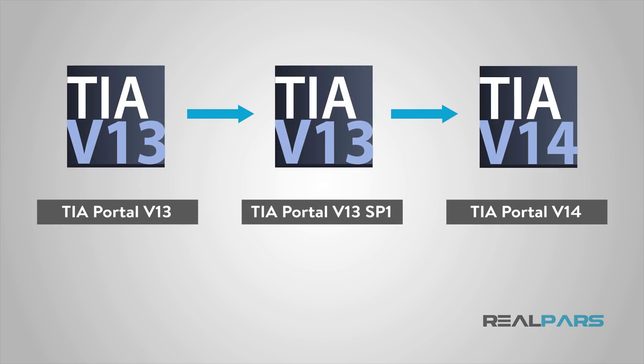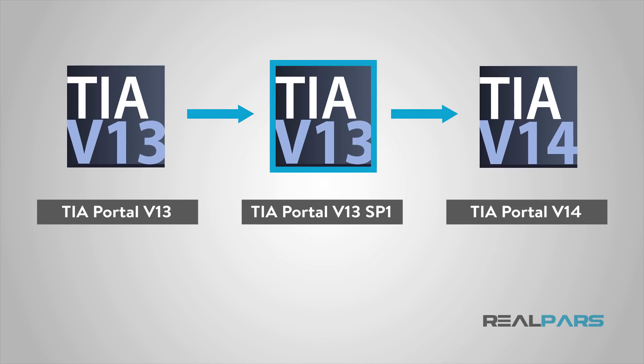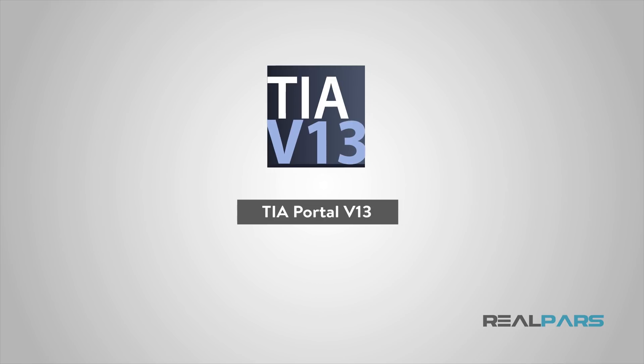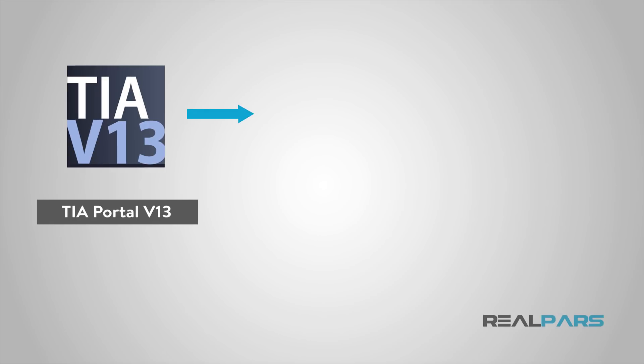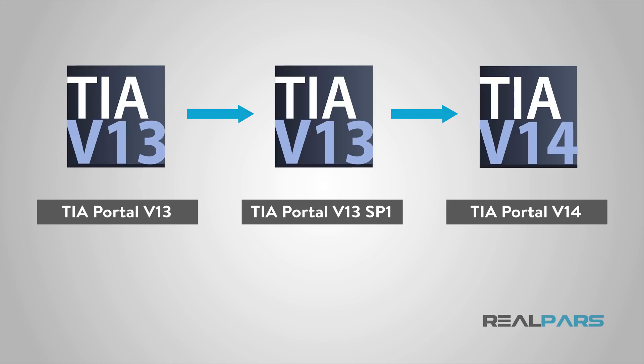So, the reason I could not open up my old project was because there was an extra layer of version between these two software. Meaning, I wanted to jump straight from version 13 to version 14. Now, I know that to be able to open up my old projects that were created in TIA Portal version 13, I first need to upgrade them to Service Pack 1 and then to version 14. If I go straight from version 13 to 14, things won't work the way it should.